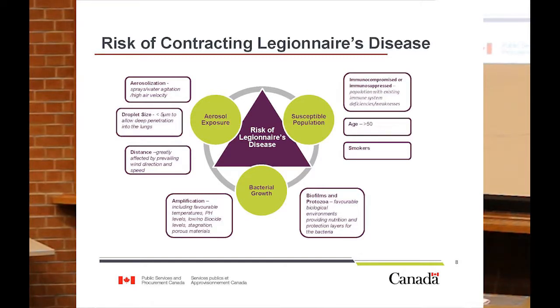For us, we view the 3 sides of the triangle as: one, you need bacterial growth of Legionella to a certain level; two, you need aerosolization of that bacteria, or potentially aspiration, though we focus more on aerosolization; and three, a susceptible population that gets exposed to it. We have zero control over the susceptible population side because we don't do medical screenings of everybody who comes into our building to assess underlying health risks, so we can't control that side at all.